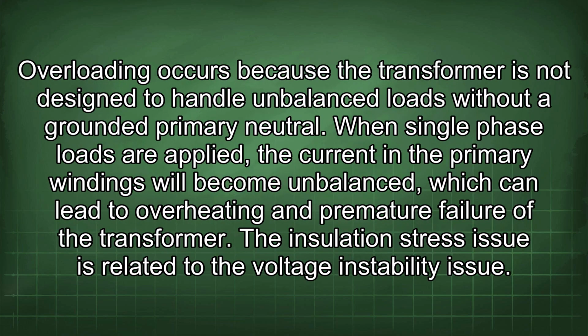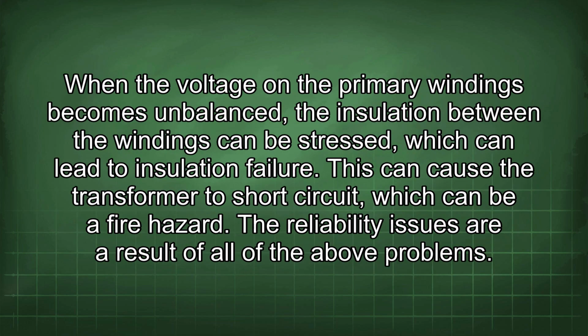Overloading occurs because the transformer is not designed to handle unbalanced loads without a grounded primary neutral. When single-phase loads are applied, the current in the primary windings will become unbalanced, which can lead to overheating and premature failure of the transformer. The insulation stress issue is related to the voltage instability issue. When the voltage in the primary windings becomes unbalanced, the insulation between the windings can be stressed, which can lead to insulation failure. This can cause the transformer to short circuit, which can be a fire hazard.